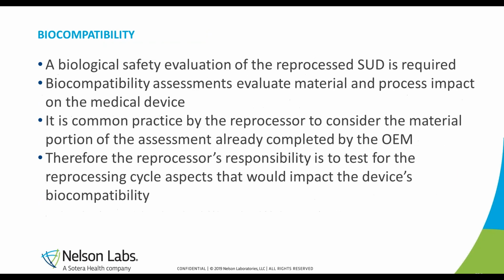A biological safety evaluation of the reprocessed single-use device is required as well. Biocompatibility assessments evaluate potential biological responses based on material of construction and processes related to the medical device. If the device is exposed to a cleaning process, special considerations should be given to detergent residuals or potential interactions between the device's material and cleaning solvents. It is a reprocessor's responsibility to test the device for any reprocessing aspects which would potentially impact the device's biological safety.